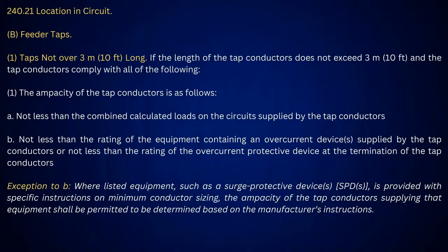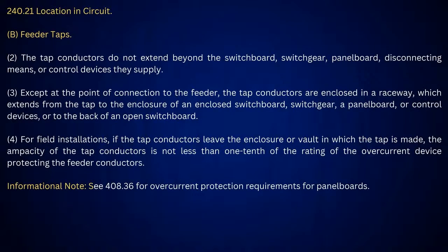Oh, wow. They were causing all kinds of grief, saying it was this big code violation. We did some extensive research on it, and come to find out, 100% legal. You could put the smallest size you want on a surge protective device because there's no load on it, and the load is paralleled with the SPD. That was a pretty interesting thing that I found out. And if you look at B4, it comes down and tells you the ampacity of conductors is not less than 1/10 the rating of the overcurrent device. So that's where I get to divide by 10.